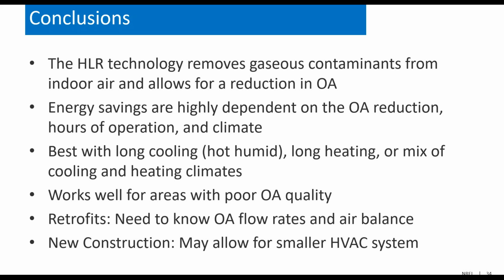But the energy savings are highly dependent on how much you're able to reduce the outside air, the hours of operation, and the climate. It's best with long cooling or heating seasons, in hot and humid climates, cold climates, or climates with both, like the Midwest, which has a lot of hot, humid, and heating seasons in winter. So it will operate in both seasons and give you energy savings.